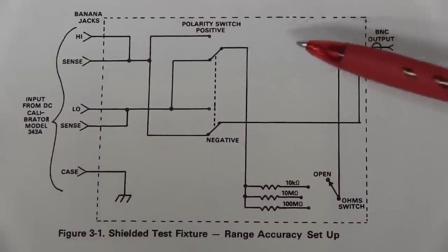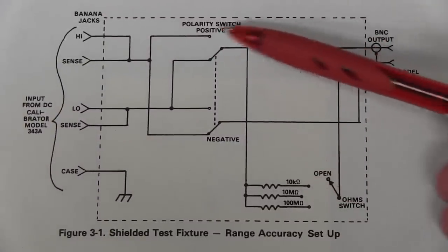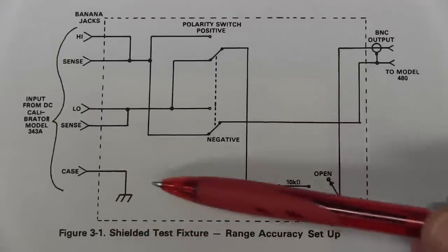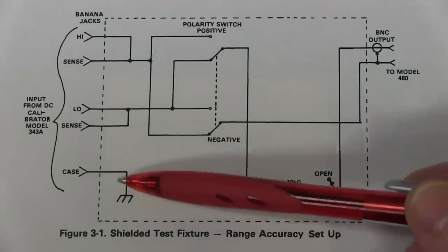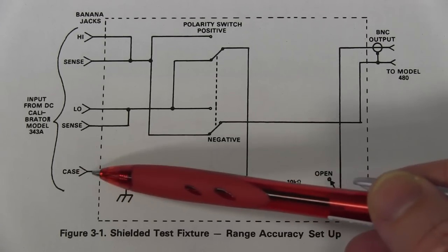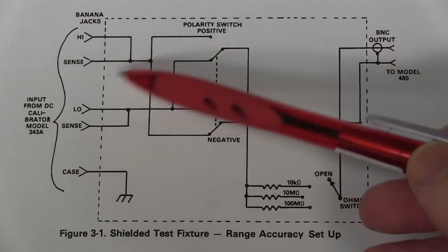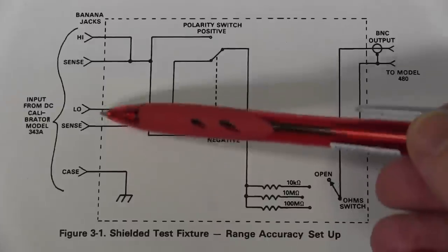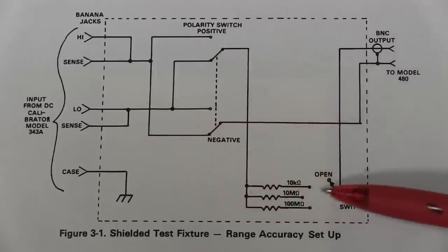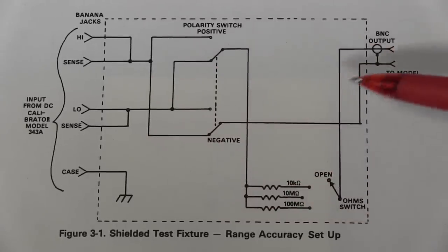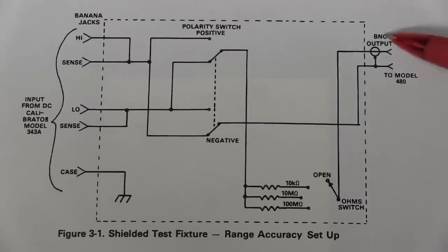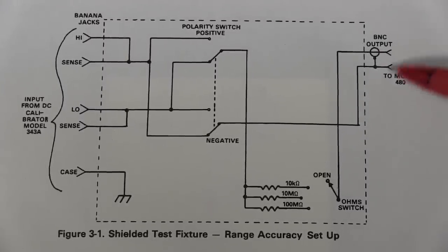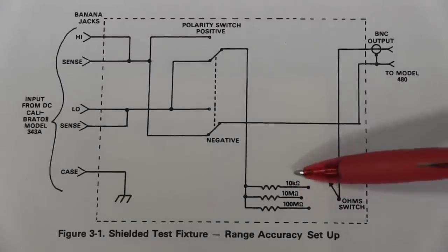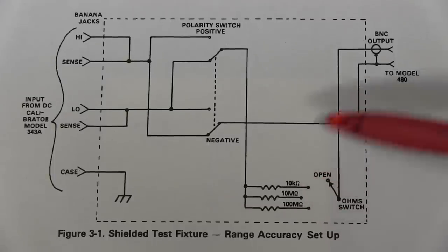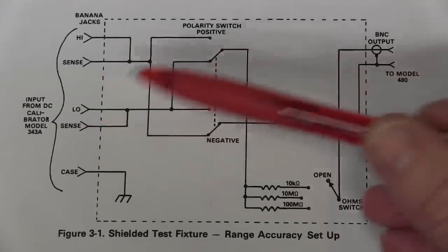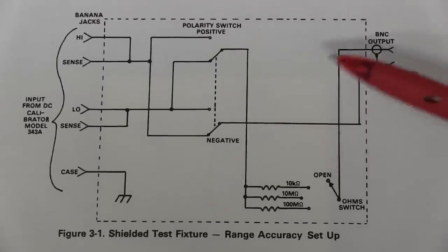And here's what I'm talking about in terms of the double shielded test fixture here. You can see that the outer case is actually connected to the earth. You can see the earth symbol there. It's connected to the earth of the DC voltage calibrator over here. And of course, we've got our low and high and our sense lines. And internally, you might also shield this circuitry from the shield, which is non-mains referenced, to the Keithley 480 over here. So you'd have the internal precision resistors. They recommend 10K, 10 meg, and 100 meg. And based on those three and the individual test voltage over here, you can generate all the required currents. But that's what you would do.